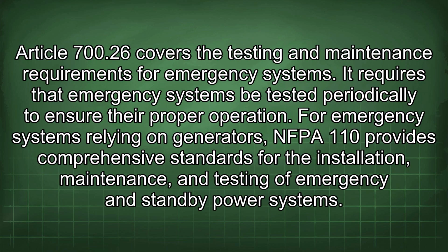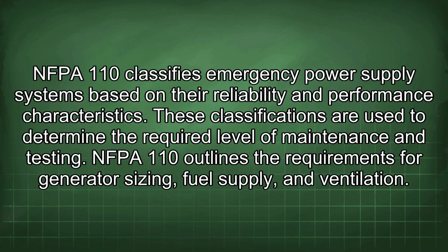Article 700.26 covers the testing and maintenance requirements for emergency systems. It requires that emergency systems be tested periodically to ensure their proper operation. For emergency systems relying on generators, NFPA 110 provides comprehensive standards for the installation, maintenance, and testing of emergency and standby power systems. NFPA 110 classifies emergency power supply systems based on their reliability and performance characteristics.